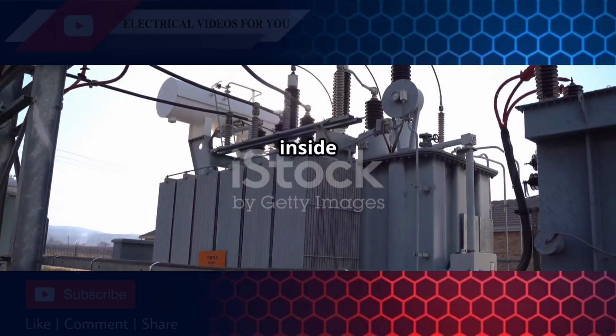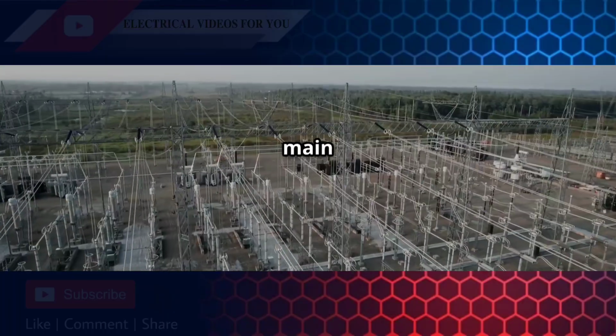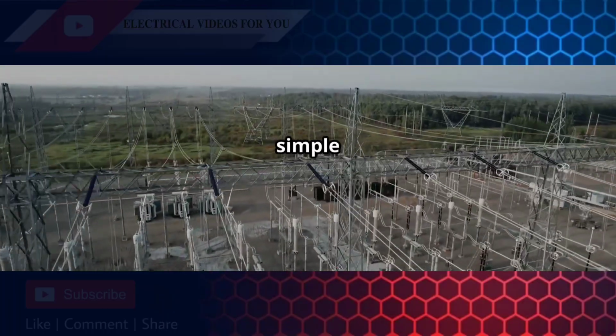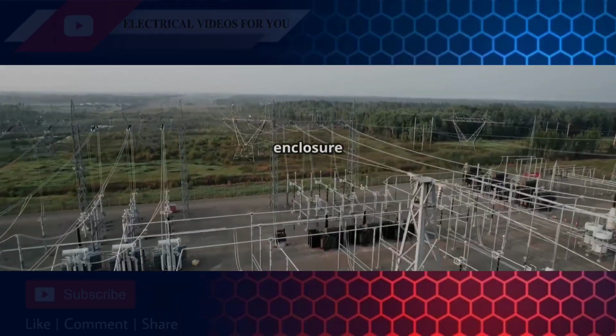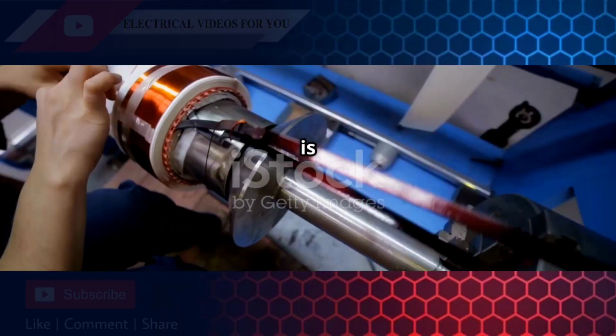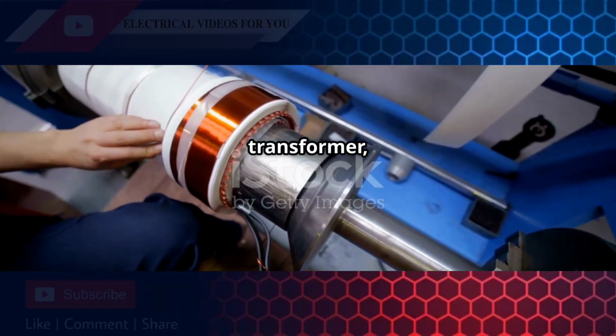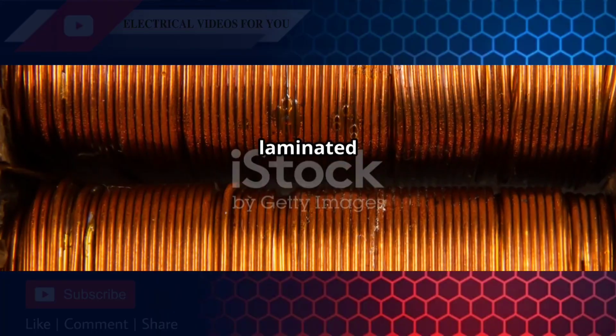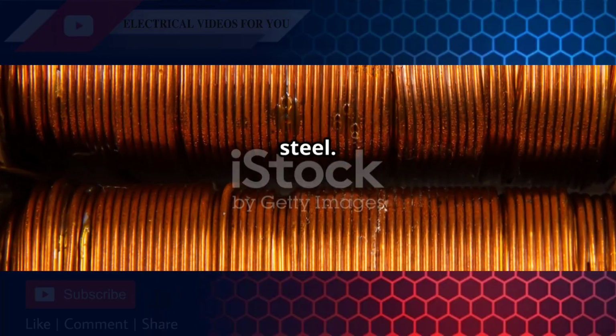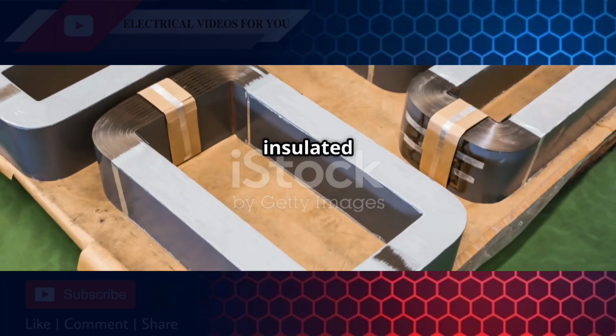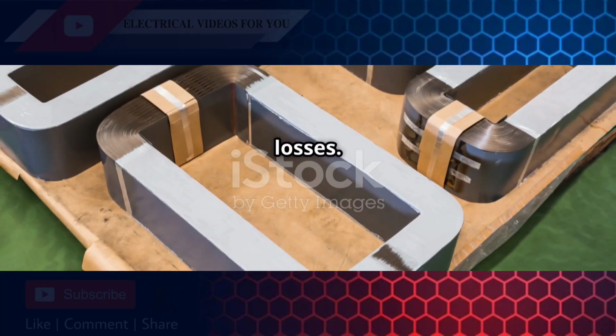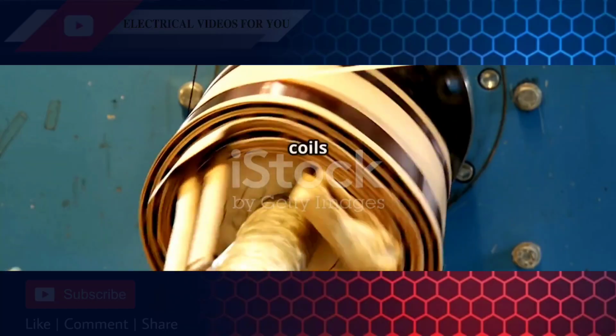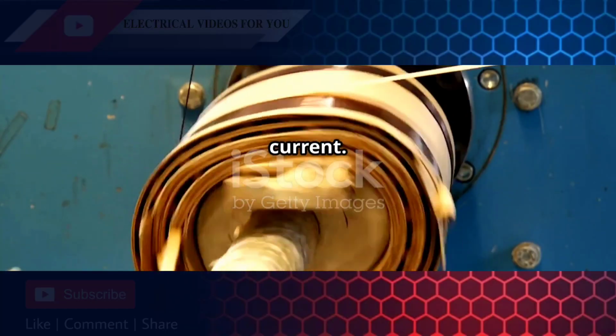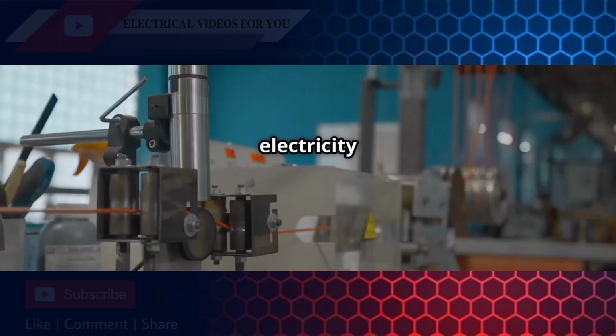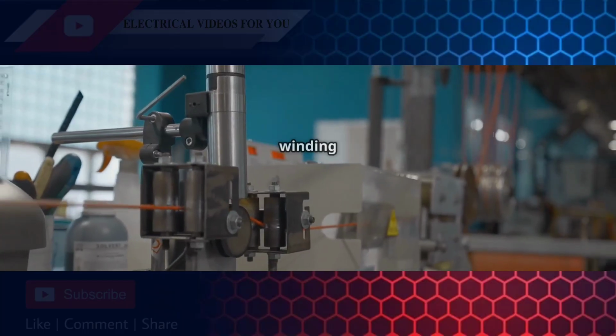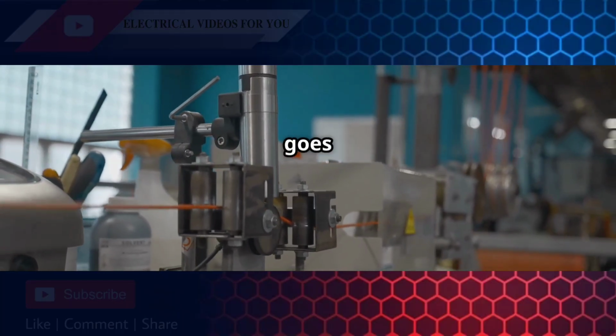Let's take a look inside this electrical marvel. The main parts of a transformer are quite simple: the core, the windings, and an enclosure or tank. The core is the magnetic heart of the transformer, usually made of thin, laminated sheets of soft iron or silicon steel. These laminations are insulated from each other to reduce energy losses. The windings are the copper coils that carry the electric current. The primary winding is where the electricity comes in, and the secondary winding is where the electricity goes out.